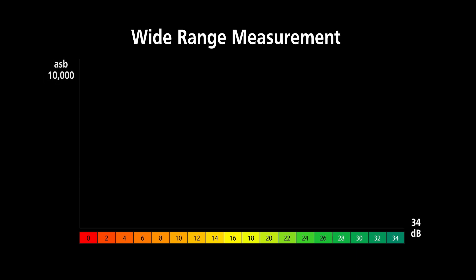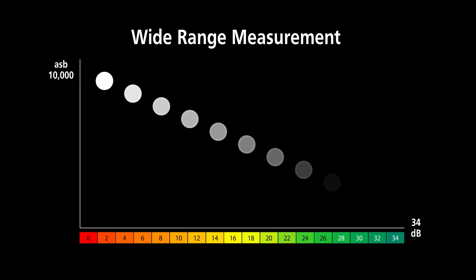Stimulus intensity ranges from 10 to 10,000 apostilbs, ensuring a wide range of measurements from 0 to 34 decibels. A maximum intensity of 10,000 apostilbs allows detection of deep scotomas. A wide dynamic range of 34 decibels ensures detection of clinically subtle scotomas in early vision loss.